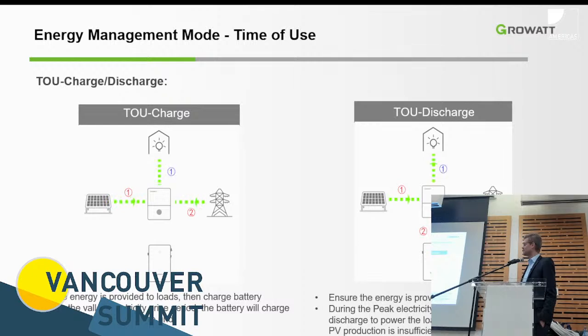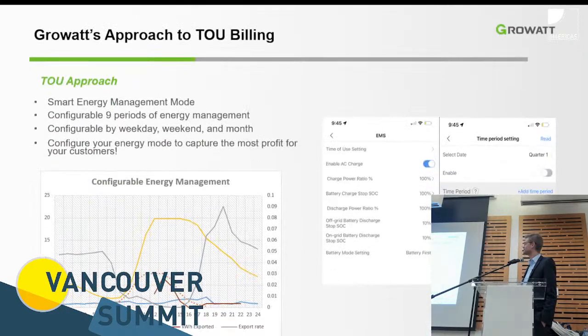Time of use is pretty much similar as we discussed. You, in an ideal world, consume the solar first because that doesn't need any storage losses. And then you use the battery and the grid, depending on the time, to supplement your load. And then that was actually the charge, charge first. So you first charge your battery, of course, either from solar or from the grid, depending on the time of use rate. And then the next part is you discharge your battery once you have the high rates on the grid to offset as much as you can.